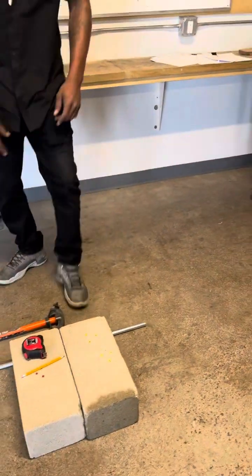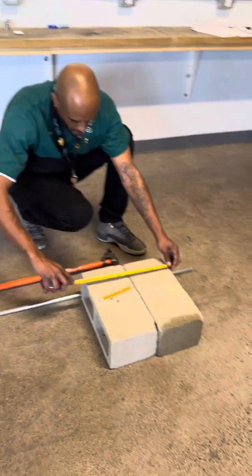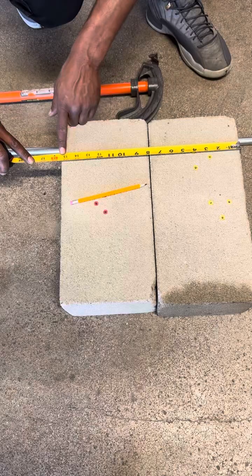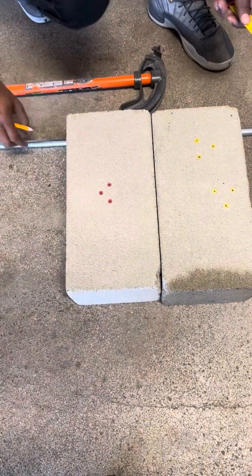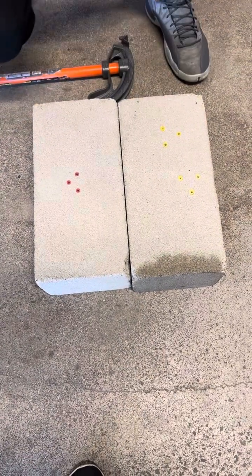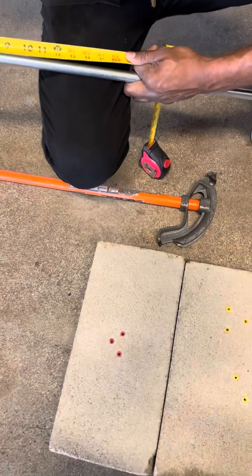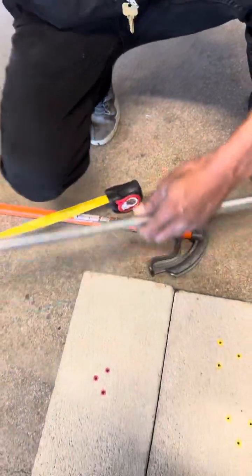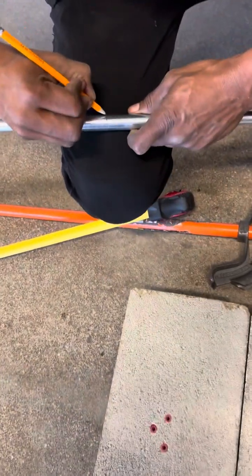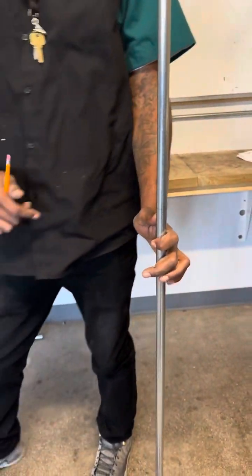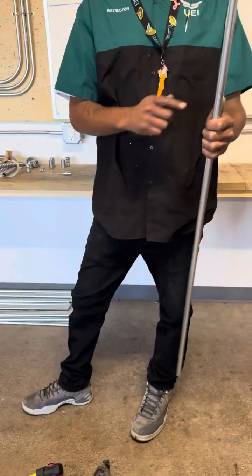So the first thing I will do is just get the distance that I'm trying to get to, okay? Which is 15 1/4. See here, it stops at 15 1/4. So I take my pipe bender, take my pipe, and I'll go 15 1/4. And a complete circle around the pipe. Okay, complete circle. That will be my first mark, as you can see. So if it slips out the piping, I can always get back to this mark, okay?